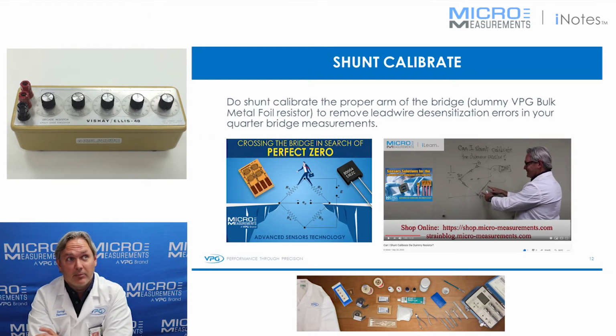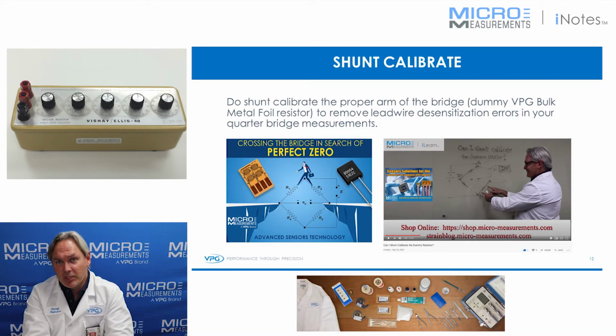Do shunt calibrate the proper arm of the bridge, typically using Vishay bulk metal foil resistors, and by shunt calibrating the proper arm of the bridge, you can remove lead wire desensitization errors from a quarter bridge measurement. Some of the other videos we have on the YouTube channel, we talk about shunt calibrating at different locations, but if you shunt calibrate the dummy resistor, that will allow you to remove the effects of lead wire resistance with a 3-wire quarter bridge circuit.